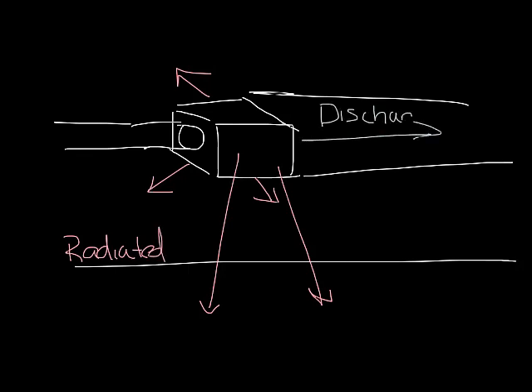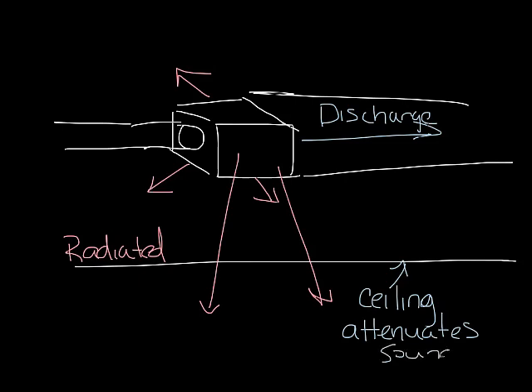The discharge sound just comes out of the discharge of the box and down the ductwork. The only thing that really is available to reduce the radiated sound going into the space is the ceiling tiles. They do a very good job at attenuating radiated sound. Applications with open ceilings can be much louder than ones with ceilings because there's nothing to attenuate the radiated sound.